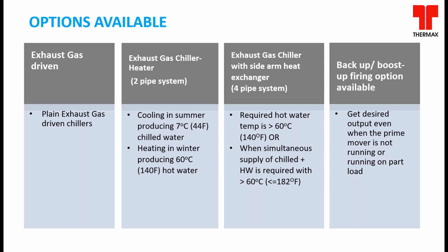A second option is an exhaust gas driven chiller heater, which recovers heat from the exhaust gases and delivers cooling in summer and heating in winter. Here there are two possibilities depending on heating systems requiring lesser or higher temperatures — both are possible with absorption systems, which can deliver hot water at 60 degrees Celsius or even 80 to 90 degrees Celsius.